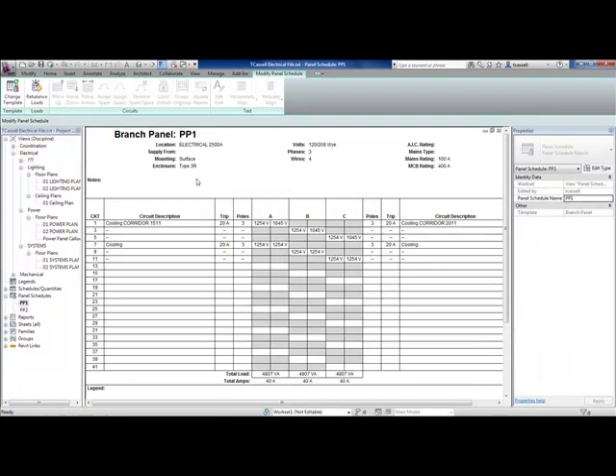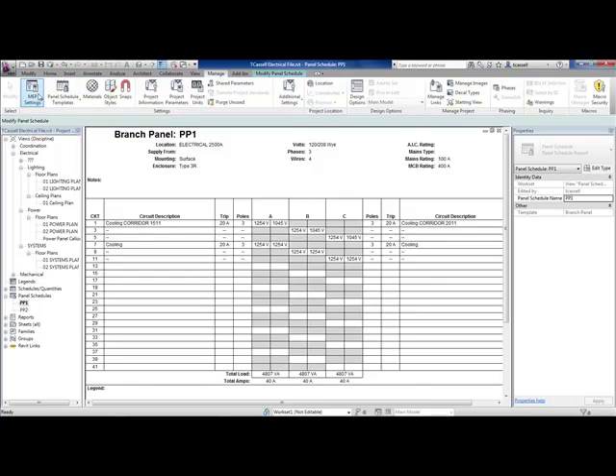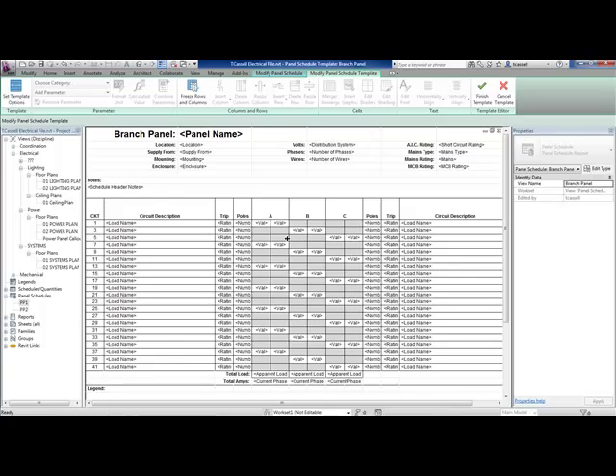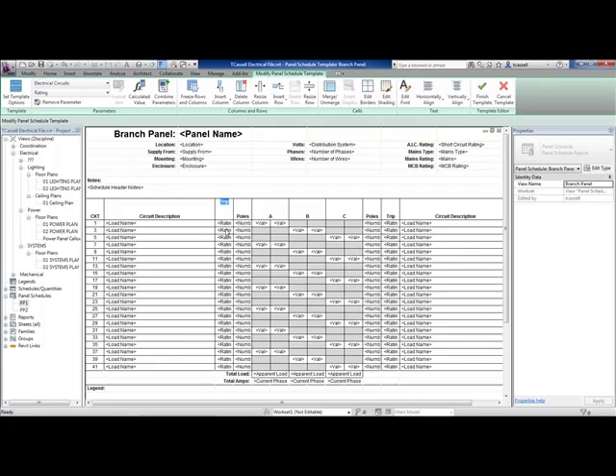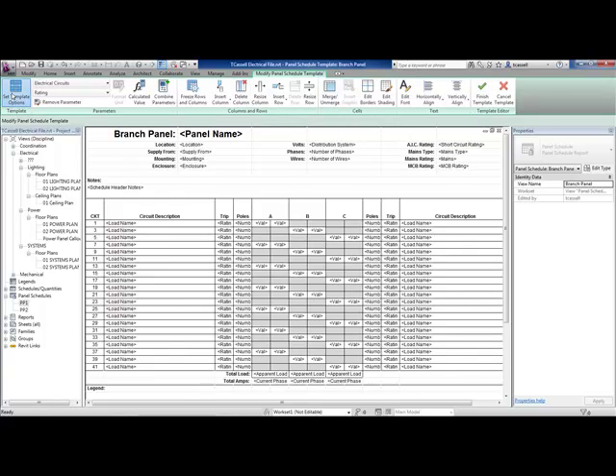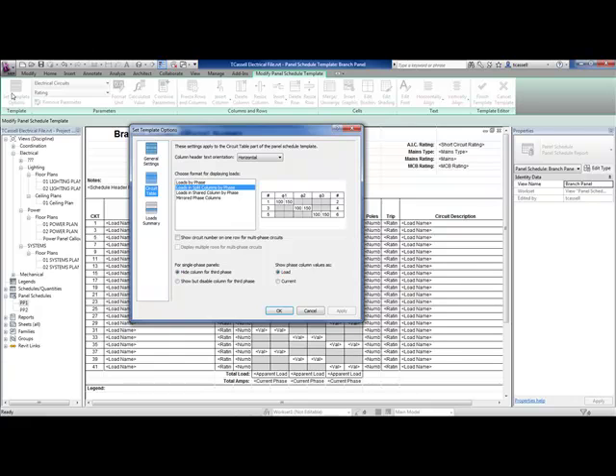In a panel schedule up until now, they're fairly flexible. You can really make a panel schedule look any way you want. We're going to see that they've made a couple more improvements just so you can customize it just a little bit better. On the Manage tab, I can go in and edit these panels. As I mentioned, they're pretty customizable. If I wanted to see the trip rating before circuit description, you can move columns, delete columns, add columns, change columns. You can really do anything you want.